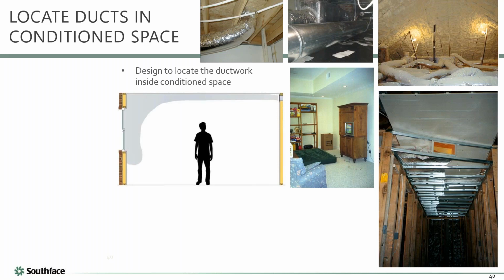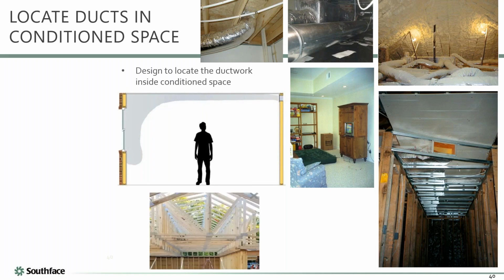And whenever you blow air out the sidewall, like you see in this picture here, and like this duct system probably has as well, you do want to make sure your terminal device is designed correctly to be able to throw the air. It'll actually cling to the ceiling. I think it's called the Coanda effect. I could be wrong on that one, but you can also frame it with a truss where the bottom chord does not go all the way across.